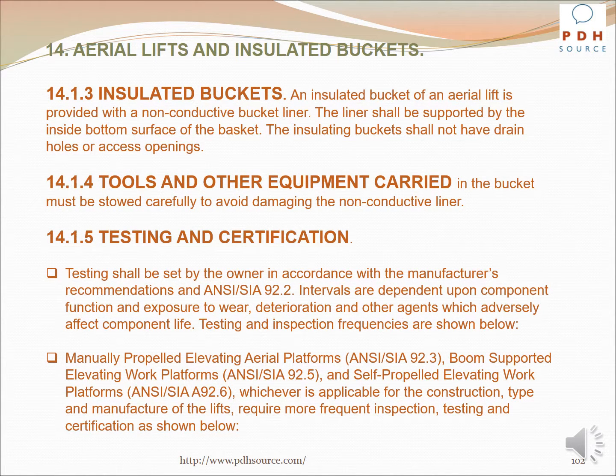An insulated bucket of an aerial lift is provided with a non-conductive bucket liner. The liner shall be supported by the inside bottom surface of the basket. The insulating bucket shall not have drain holes or access openings. Tools and other equipment carried in the bucket must be stowed carefully to avoid damaging the non-conductive liner.